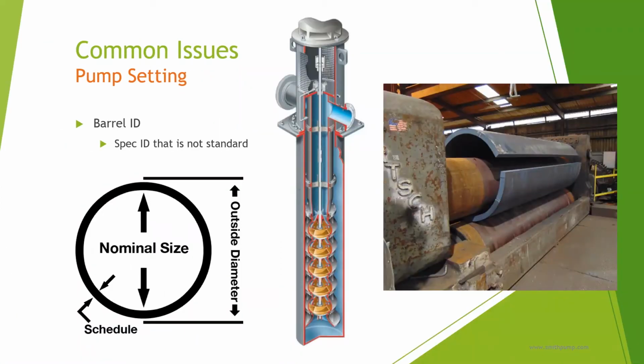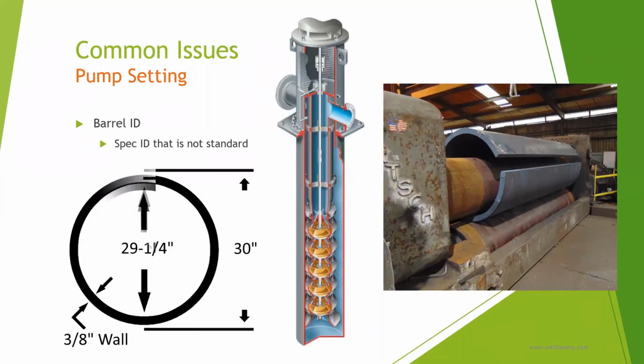Sometimes we see a spec ask for a specific barrel ID. While it can be done, the cost associated may not be worth it. When making a suction barrel, we use plain Jane regular old pipe during fabrication. Any pipe larger than 12 inches is sold by the outside dimension, not the inside. So let's take a 30-inch pipe, for example. If the OD is 30-inch with 3/8 wall, this makes the inside diameter 29¼ inches. If the spec wants a 30-inch ID barrel, we have to roll plate to make a 30-inch ID barrel. So be aware the added cost for this extra 3/4 inch ID typically isn't worth the rolling and welding cost on small pumps, but it could be justified on larger equipment.